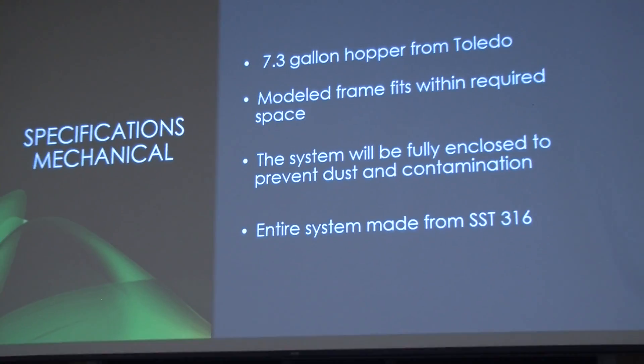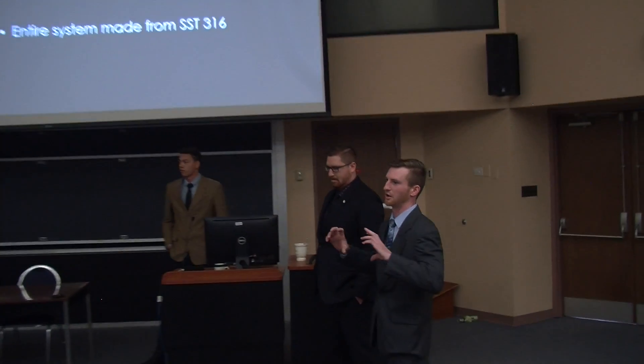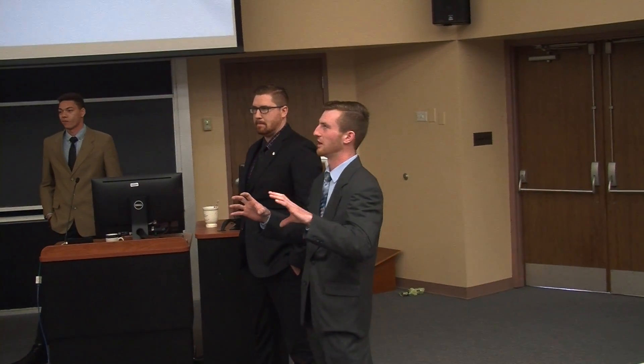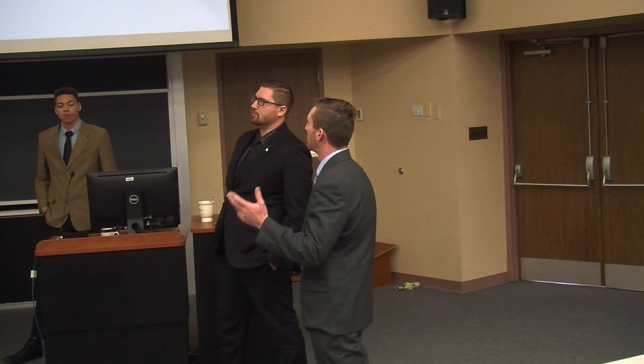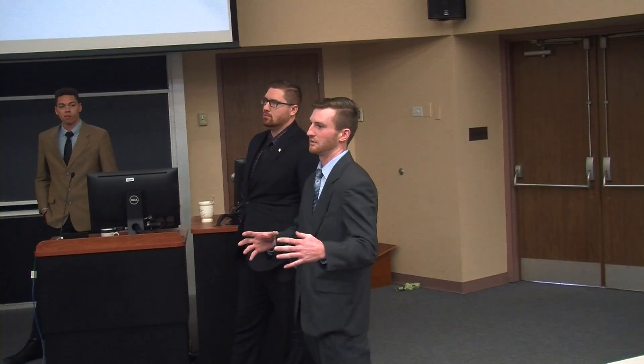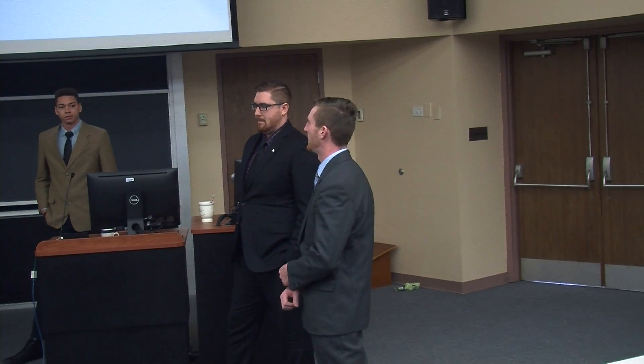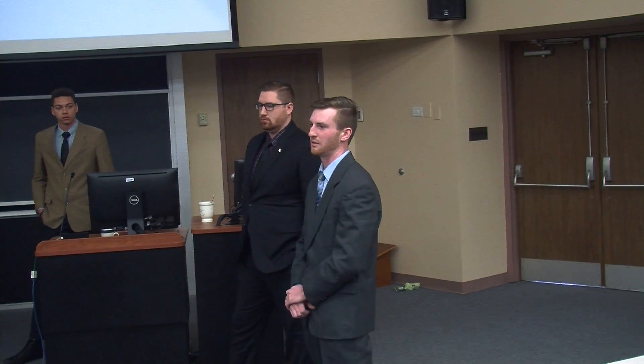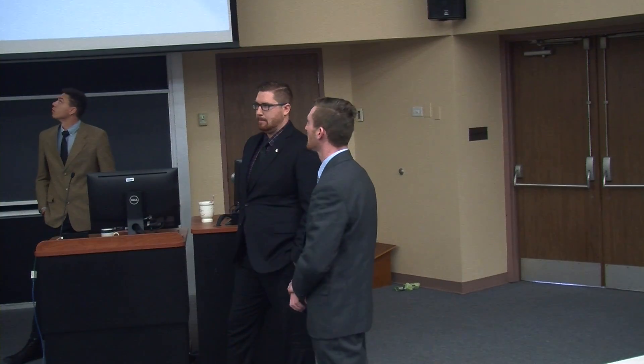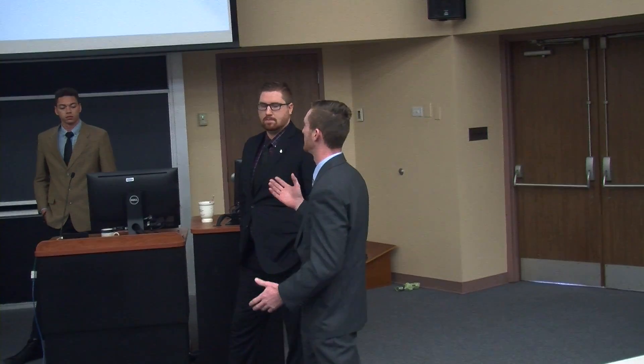Our mechanical specifications: we will be using a 7.3-gallon hopper from Toledo Metal Spinning. It's a metal-spun hopper — they spin the metal into a funnel shape. 7.3 gallons is equal to about 1 cubic foot of material. The model will fit within the floor plan of their accessible area on the plant floor. It will be fully enclosed to prevent any dust contamination. Any dust means product lost. The entire material-contact system must be stainless steel — we will use a combination of 316 and 304 stainless.